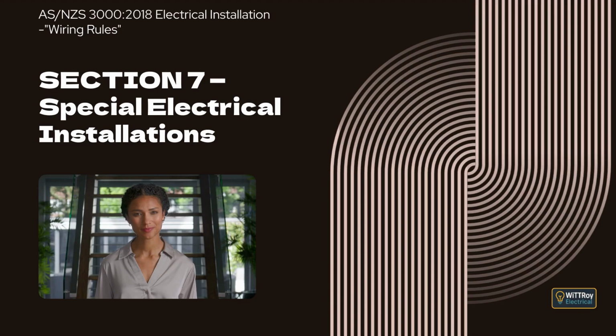Clause 7.4.6, supply to multiple items of electrical equipment. This clause explains that where a separated circuit supplies more than one item of electrical equipment, all exposed conductive parts of the separated circuit must be connected together by an insulated equipotential bonding conductor that is not connected to earth, protective earthing conductors, exposed conductive parts of other circuits, or extraneous conductive parts.